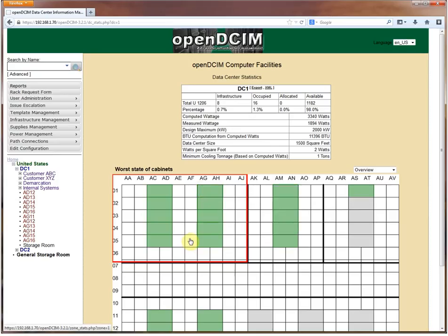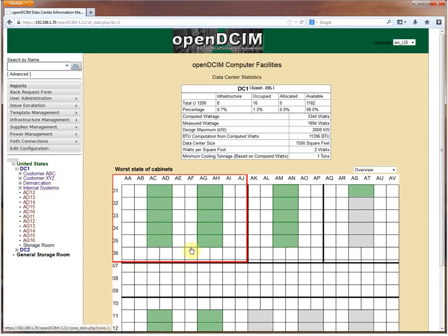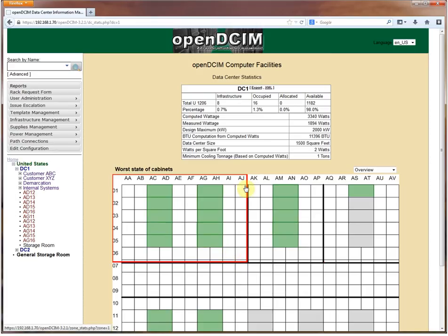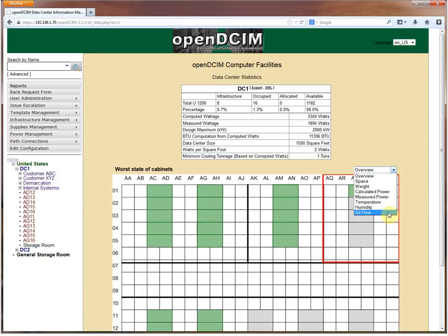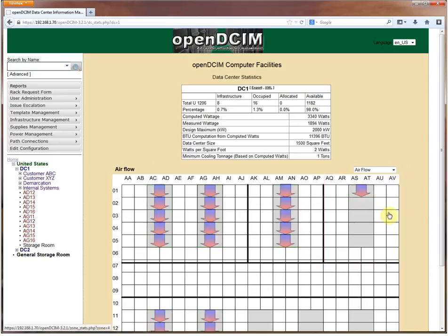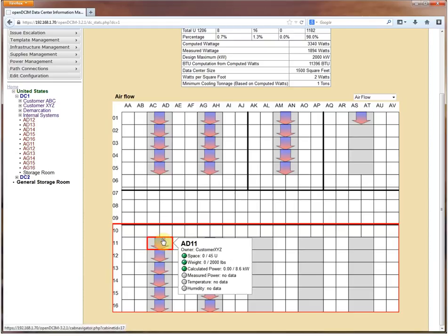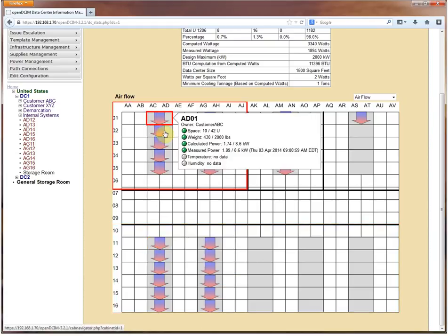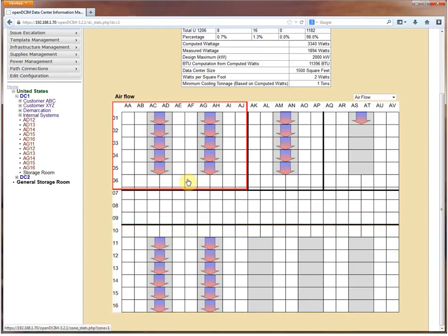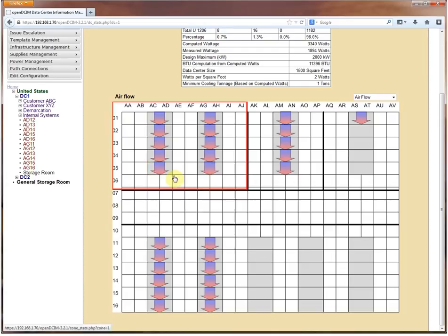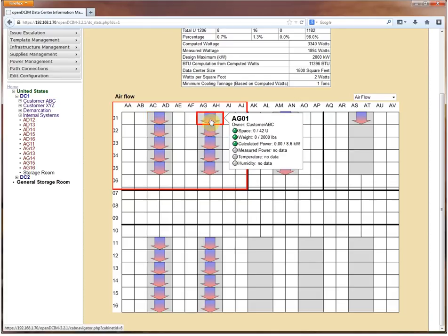The way that we determine the order that you display something in is by knowing which side of the cabinet is the front side, the side that gets the air intake. How do we know what it's currently set at? You can come over here to the dropdown and you'll notice there's now an airflow that you can choose and we have arrows that indicate what the front side is. The blue side is the side that is the air intake, that's the cold side, and the red side is the exhaust, that's the hot side.